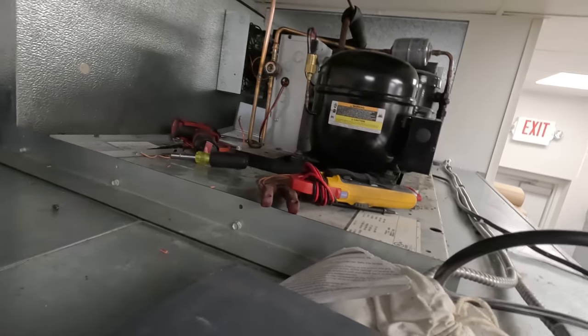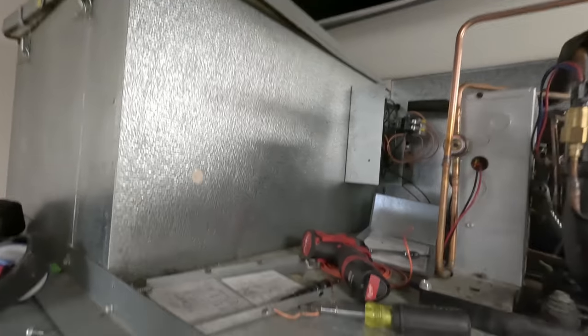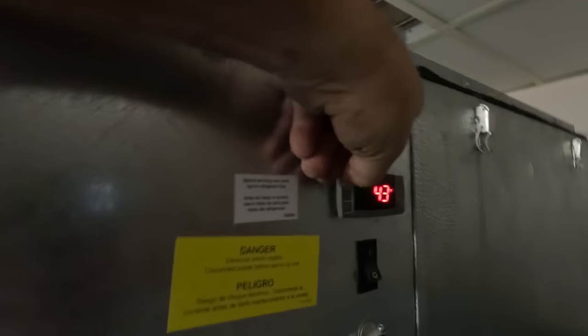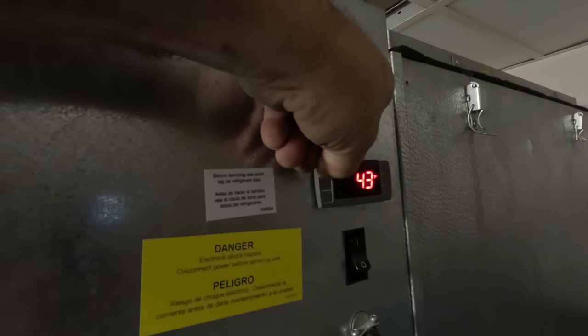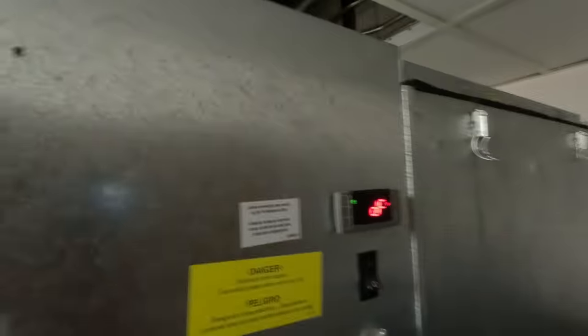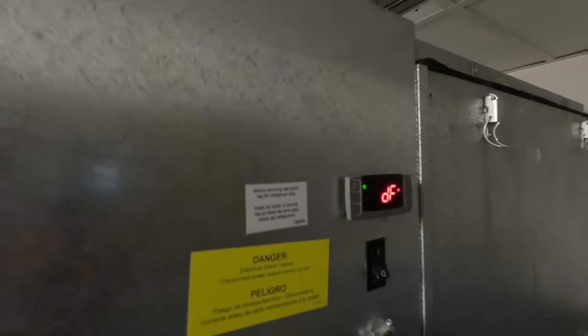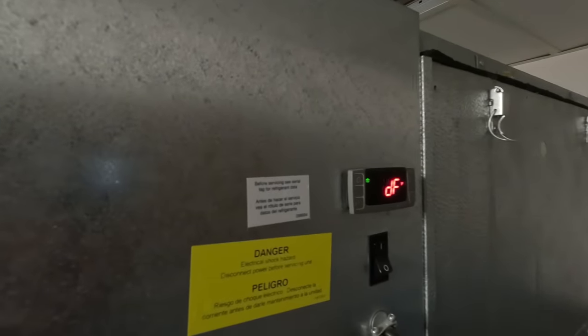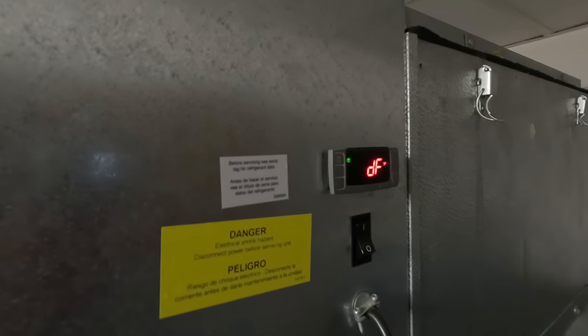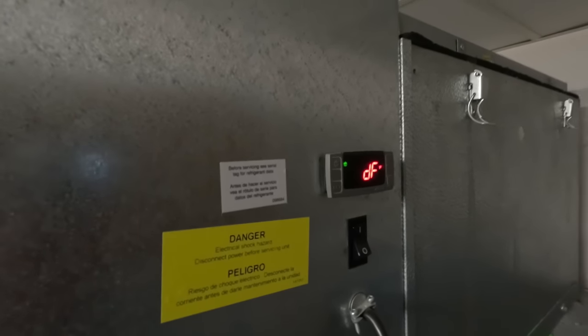So now we've got to melt that coil. Before I end up melting that ice and making it warm in there, I'm going to test it out first, make sure it works. So you can see the fans running there and the fans are running in there. Let's put this thing into a defrost and see if they shut down. Making sure nothing's going to short out. Everything's insulated. Okay, let's hit the defrost button. Look at that. Compressor shut off. Not bad for an immature YouTuber. Good deal.